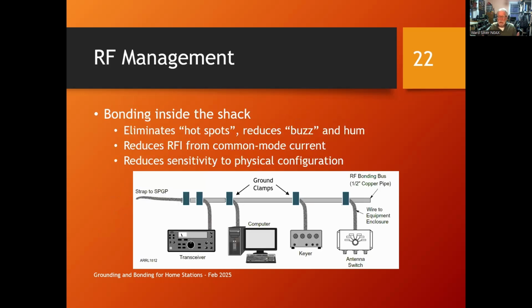And a lot of us have already done this to some extent in our station. You've seen this picture a million times, maybe in a license guide, maybe in a handbook, whatever. Usually it's a 1/2-inch copper pipe because that's the cheapest they've got at the store. And then everything is connected to that copper pipe. I mean everything, even the antenna switches should be connected to that copper pipe because they are exposed metal, just like a keyer or a computer or a transceiver. So you do not want that exposed metal to suddenly go up to a lot of volts. So you bond that to this copper pipe.